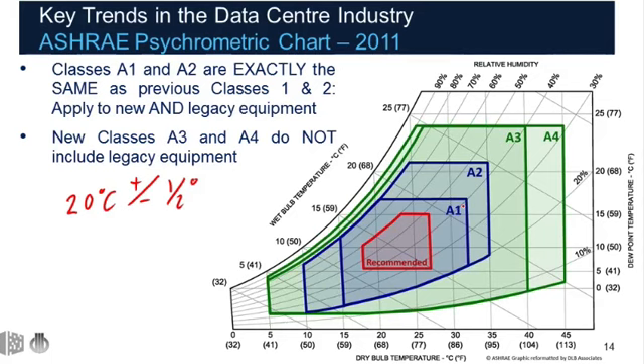If we look at the psych chart, we've published this, and all the IT manufacturers agree with it, they're all on the committee. Even for legacy equipment in this A1 class and A2 class, it applies to legacy equipment, as it states right here. What this is showing is, what's the point? It's not about a single point. If we look at the 20 degrees here with that small band, that's nothing.